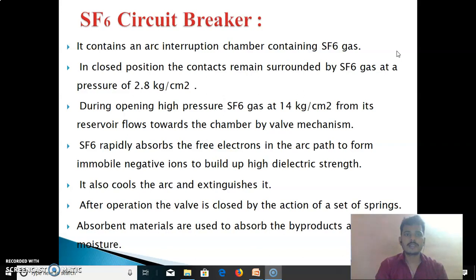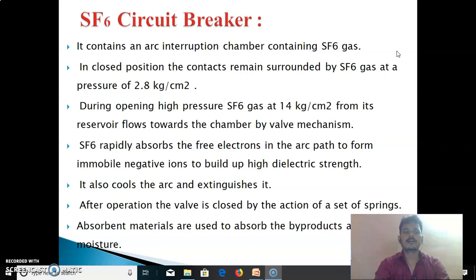Next, we see the SF6 circuit breaker. The fixed contact and moving contact are placed in SF6 gas, which is why it is called an SF6 circuit breaker. It contains an arc interruption chamber filled with SF6 gas. In the closed position, the contacts remain surrounded by SF6 gas at a pressure of 2.8 kg/cm². During opening, high pressure SF6 gas at 14 kg/cm² from its reservoir flows towards the chamber by a valve mechanism. SF6 rapidly absorbs free electrons in the arc path to form immobile negative ions, building up high dielectric strength. It also cools the arc and extinguishes it. After operation, the valve is closed by the action of a set of springs. Absorbent materials are used to absorb byproducts and moisture.